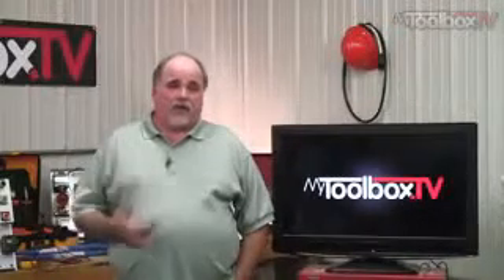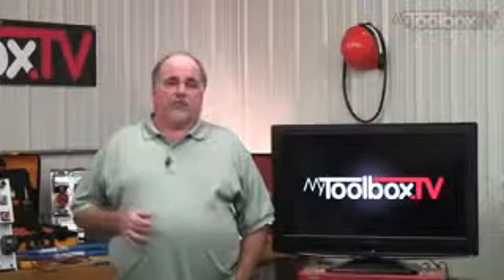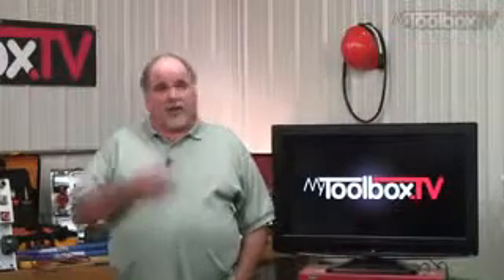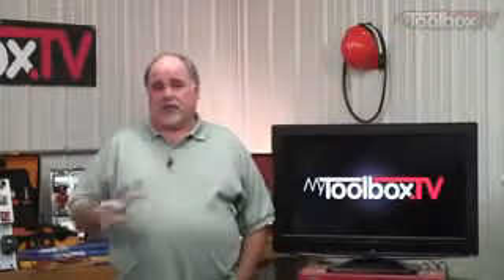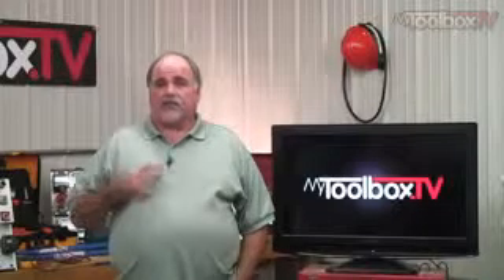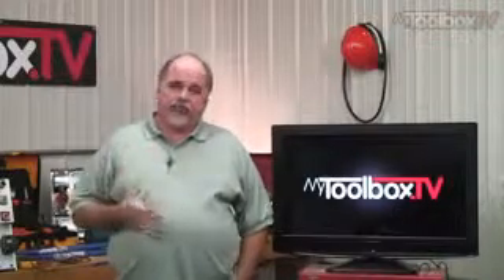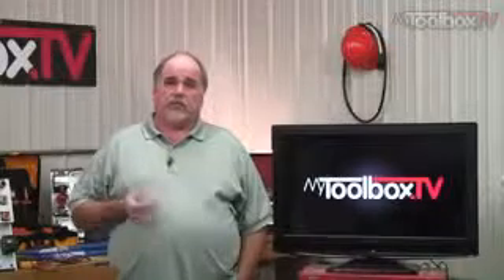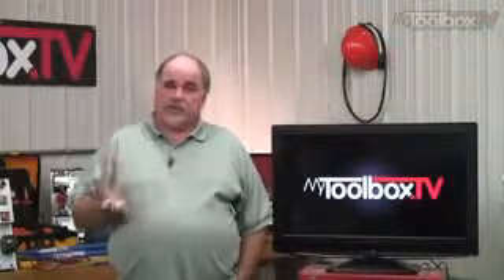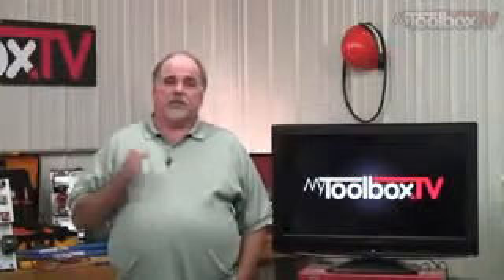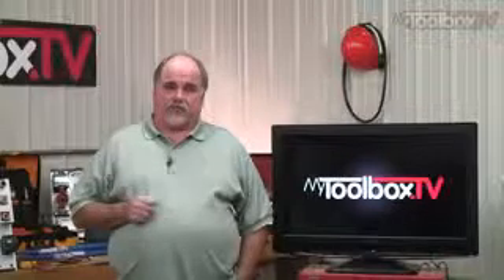Today I want to talk about residential transformers, that transformer that's on a pole outside your house, or maybe it's on the ground on a pad. We're going to talk about how they're connected, how they get you the 240 volts or the 120 volts you need for receptacles, lighting, and what have you. So let's take a closer look at residential transformers.